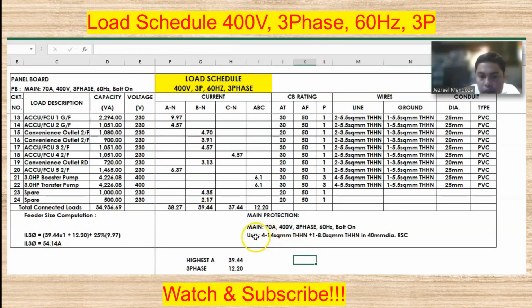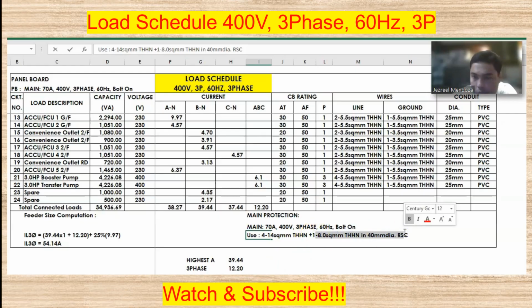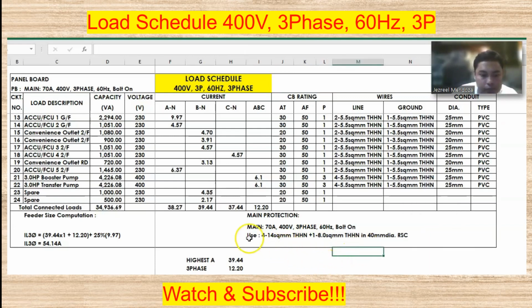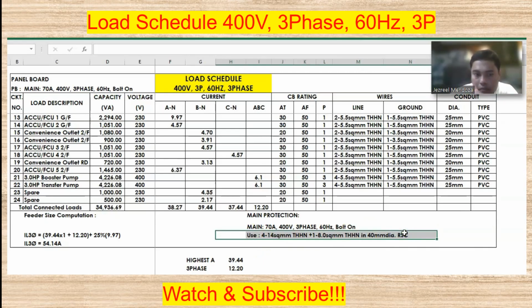That is 3 lines na 14 square mm plus 1 neutral plus ground na 8.0 square mm in a 40 mm diameter rigid steel conduit. And then for this wire, be sure that you have 1.25. Meron kang parang allotted na 80% doon sa wires capacity.